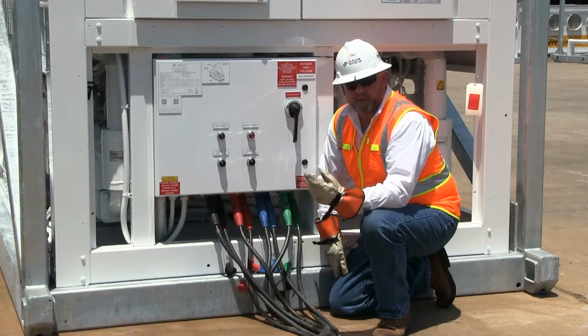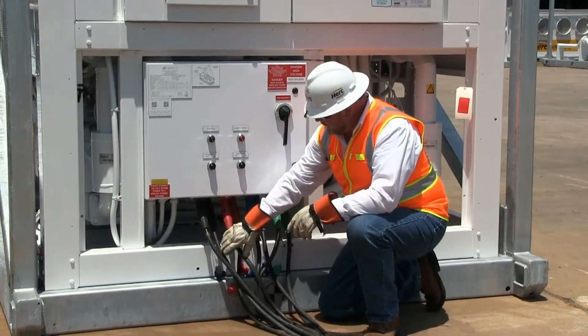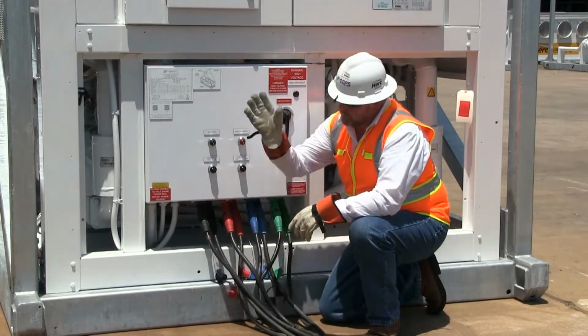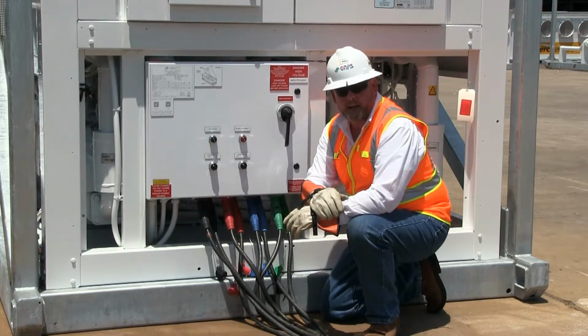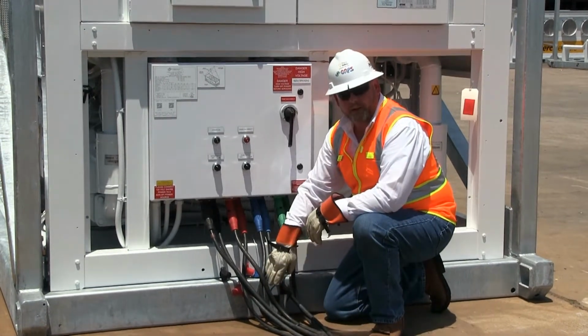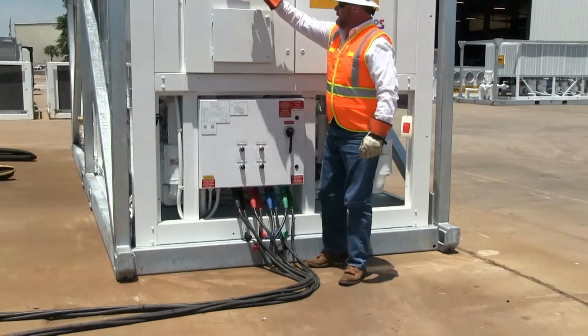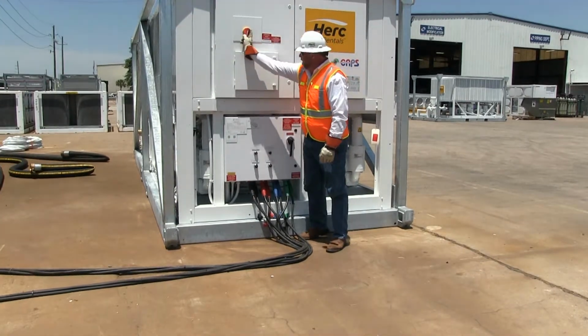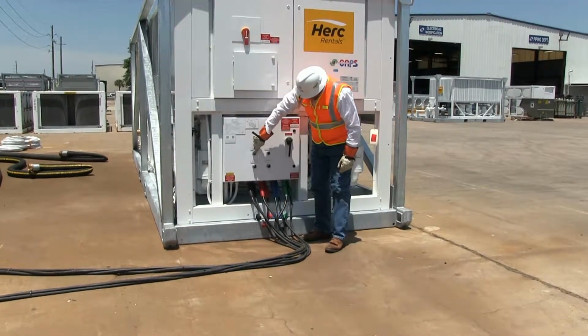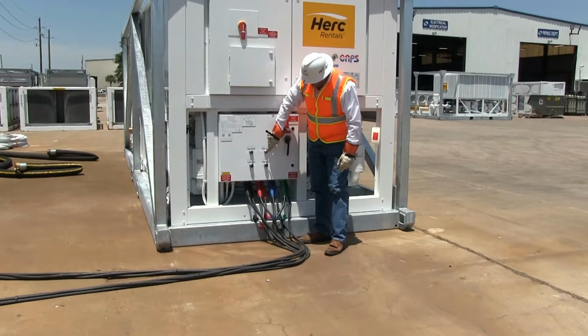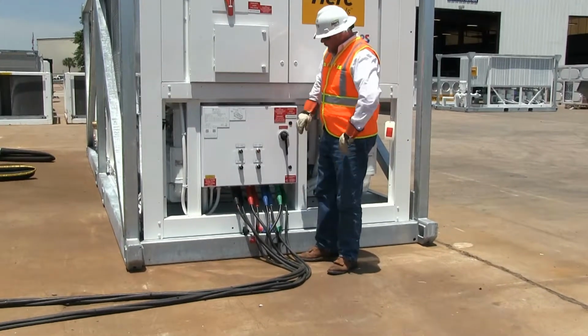Okay, we've reversed phase A and B as indicated here with L1 and L2. We've removed our lockout tagout from our permanent power source. Our cables are now energized. We're going to go up and turn the main power disconnect back on again. Now we have a power light and our phase incorrect light is off. So now we're powered up and ready to go.